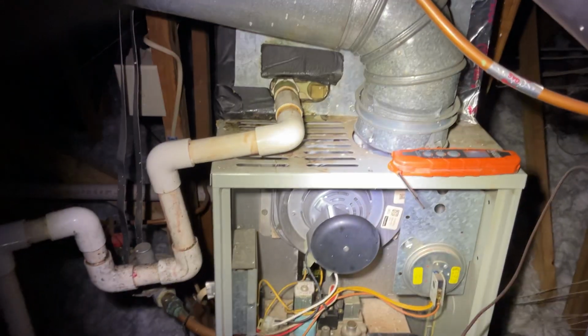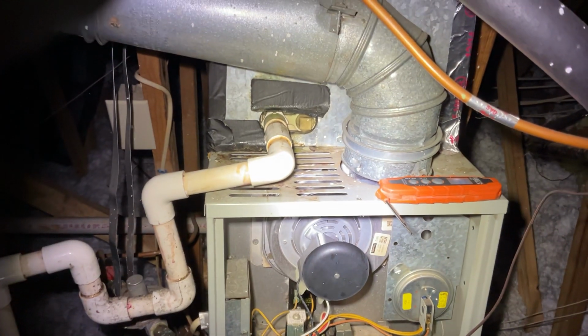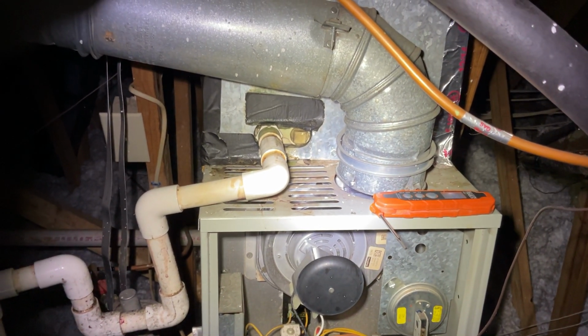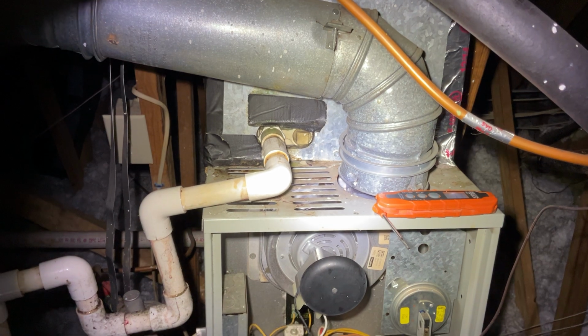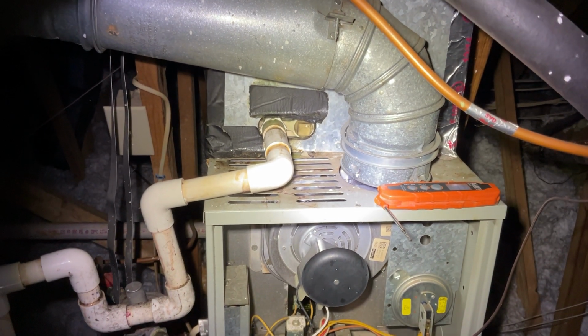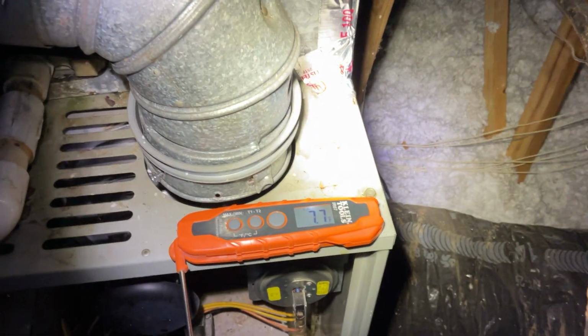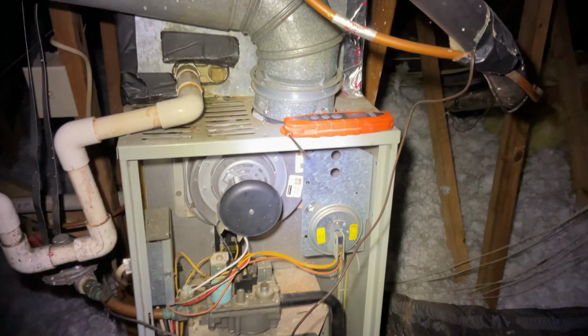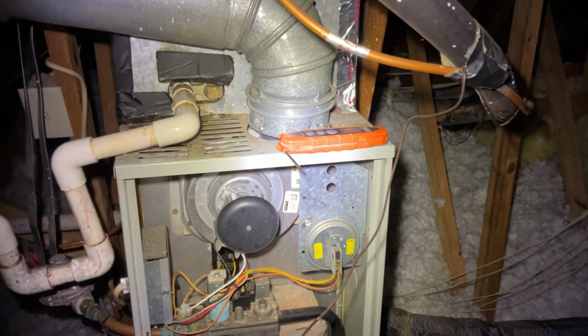But the air filter was dirty, which sometimes slows the speed of the air down through the evaporator coil, and sometimes that can inflate the number too. Here I was getting a temperature differential of 7.7 degrees. No, that is nowhere near 15 degrees, which is the minimum I wanted to see.